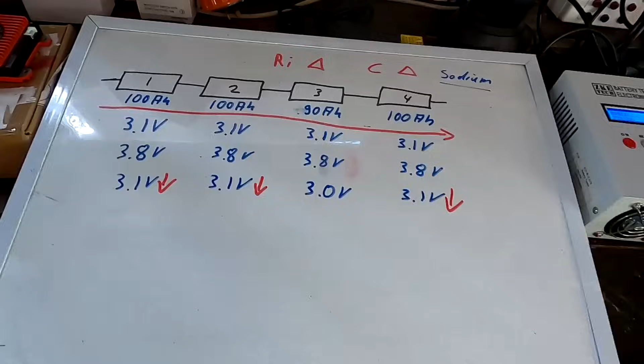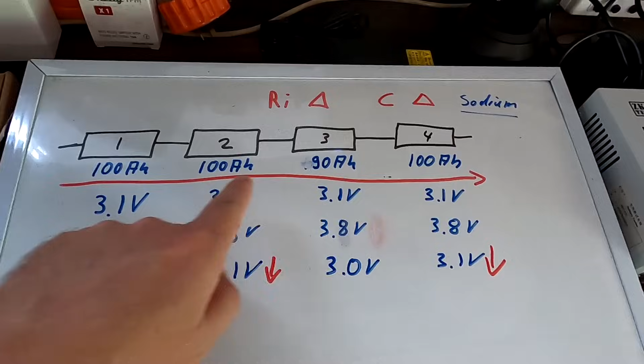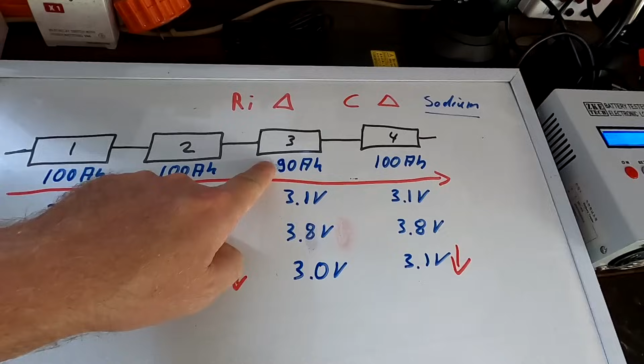So even from a technical perspective, we can balance sodium batteries at any voltage. This is precisely related to your state of charge. You should not do that because of exactly that. The balancer would be constantly working, constantly, because your cells are different. They don't have the same capacity. Never, ever. So, I think this is why it is important, even with sodium batteries, you just do a top balancing. You bring your cells to 3.8 volts, balance them, and then let it go. When the battery is discharging then, cell number 3 will determine your overall capacity of the battery.